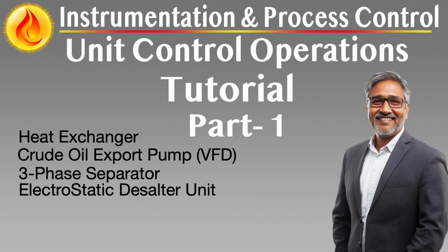Modern VFD pump control strategies are built around feedback from multiple process variables, such as export flow rate, pipeline pressure, tank levels, and valve positions. These signals are used to establish control loops where the VFD speed set point is calculated by a flow controller or pressure controller, often with override conditions based on safety or process constraints. The VFD acts as the final control element, adjusting pump RPMs to match system requirements. High-resolution sensors and fast-response PLCs ensure loop stability even under turbulent or high-inertia flow conditions.